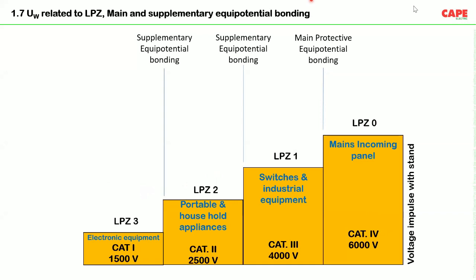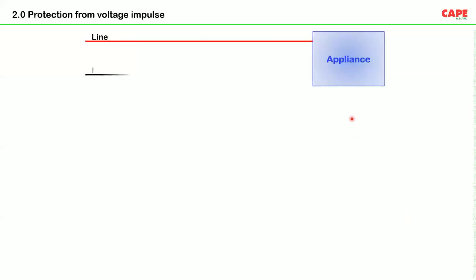With respect to lightning protection, these are categorized into lightning protection zone 1, zone 2, zone 3, whereas with respect to electrical safety, it is classified, for example, between zone 0. Sorry. Main protective equipotential bonding, then supplementary equipotential bonding, and so in this typical fashion. So equipotential bonding shall be made with respect to electrical safety, lightning protection, transient protection, and so on. Now, let us look at our appliance.